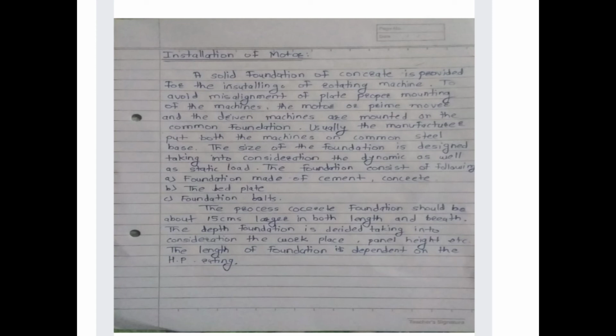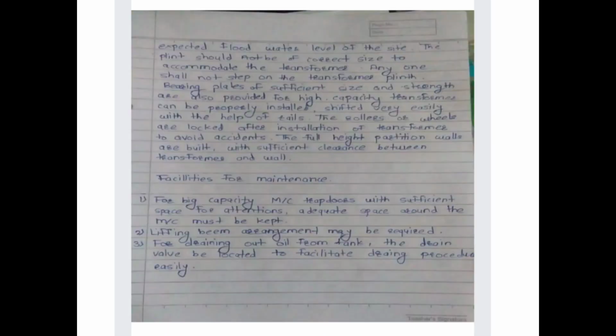Usually the manufacturer puts both the machines on a common steel base. The size of the foundation is designed taking into consideration the dynamic as well as static load. The foundation consists of the following: first, foundation made by cement or concrete, then the bed plate, third, the foundation bolts. The concrete foundation shall be about 15 cm larger in both length and breadth. The depth of the foundation is decided taking into consideration the workplace, panel height, etc. The length of the foundation depends on the HP of the rotating machine.